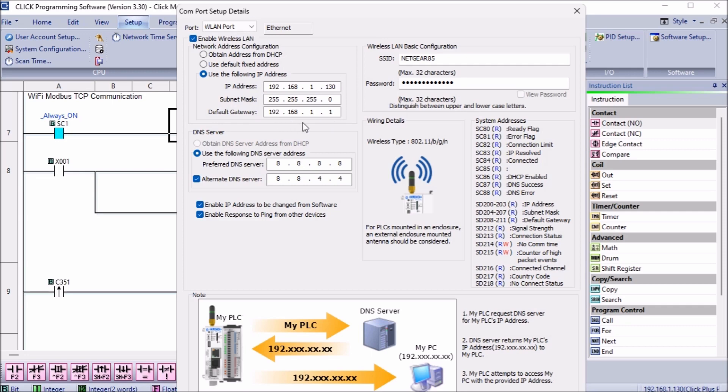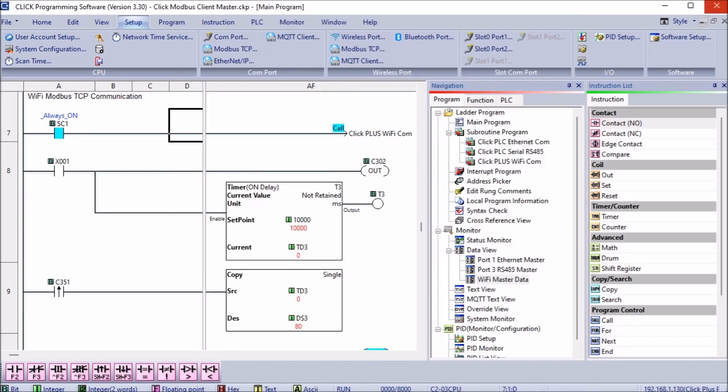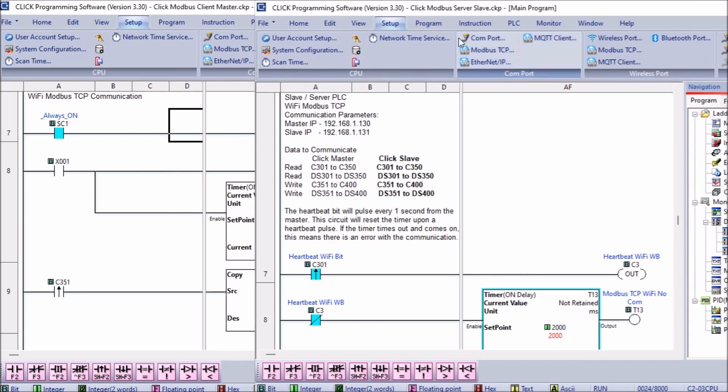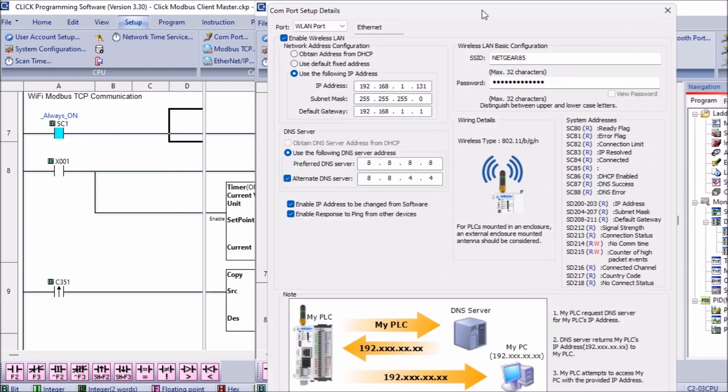This IP address is used to determine where the message will be directed using Ethernet. TCP IP refers to the transmission control protocol and internet protocol, which provides the transmission media for Modbus TCP messaging. The primary function of TCP is to ensure that all packets of data are received correctly, while IP makes sure that the messages are correctly addressed and routed. TCP IP is a transport protocol and does not determine what the data means or how the data is to be interpreted. Modbus TCP protocol will be the data and each Click PLC will interpret this information. This is how information will be transferred between the two Click PLCs using Wi-Fi.